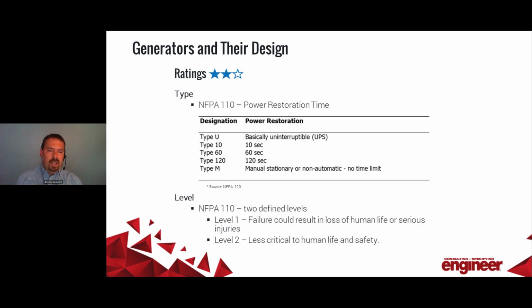And then also you have levels. NFPA 110 defines 2 levels. Level 1, failure of the system could result in the loss of human life. Level 2 is less critical, as where a minor injury may be sustained. So it's important that we understand what our level, what our type, what our classification, what our tier is early on in the project.